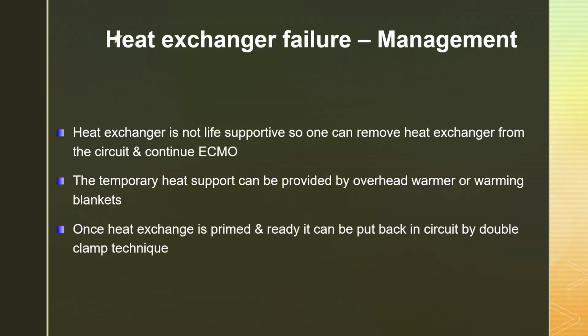The last part is heat exchanger failure. I think that's probably the simplest but difficult to diagnose. The reason is that if you are not monitoring temperature, it's going to be difficult to diagnose. If the machine fails or is not working, you can have hypothermia, or if it malfunctions, you can have hyperthermia. It can occur either way. You might get the signs of hypothermia, such as your saturation suddenly starting to improve. You are very happy that your saturation is good, but it's not always good. It might just be hypothermia that is increasing your saturation.